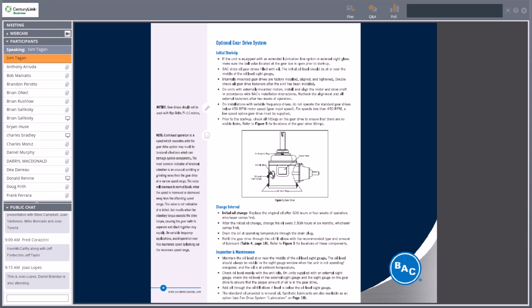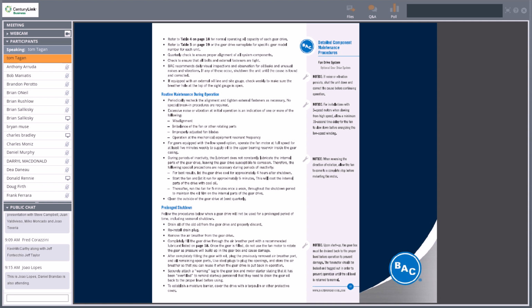Again, BAC also and most manufacturers offer optional gear drives. I'm sure you have plenty of towers. I believe the towers on this building actually have a gear drive. So again, another list of things to look out for. With a gear drive, the oil change and making sure that the gear is well oiled is important to the life of the unit. So your routine maintenance is located on this page.